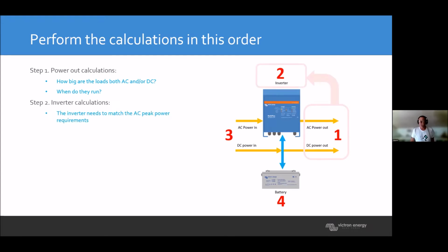For the inverter calculation, we make sure the system is big enough to handle the loads coming in, including peak loads. When I talk about peak load, if you are off-grid, you often have pumps, sometimes 3-phase pumps, that take a lot of peak power when starting up, and the system must be able to handle that too.